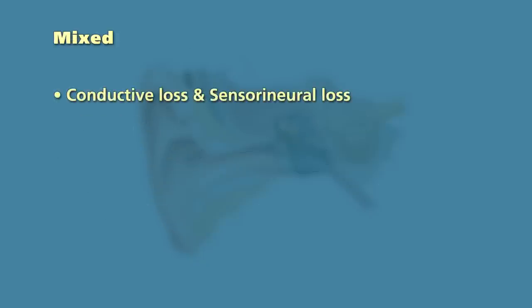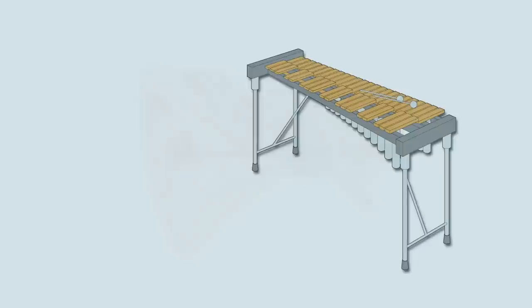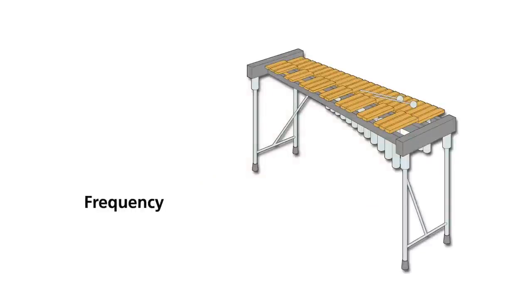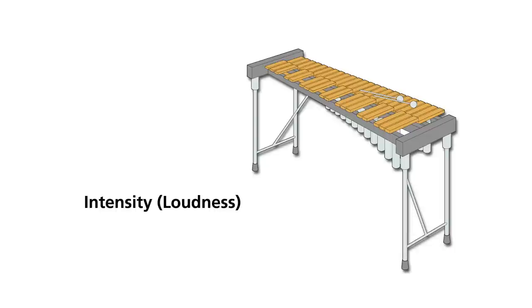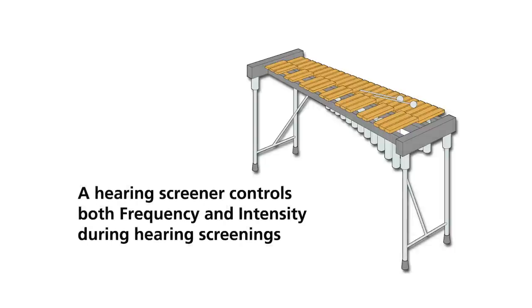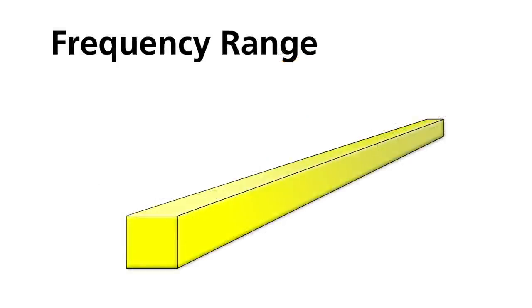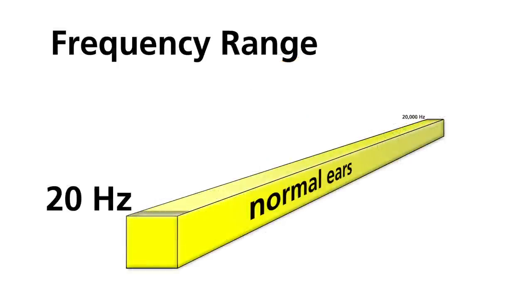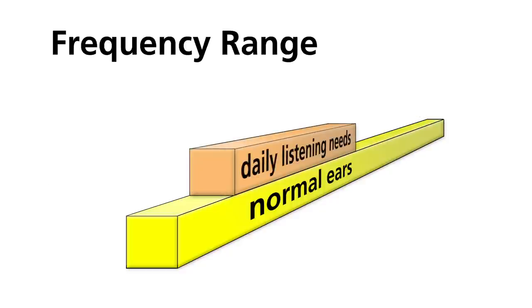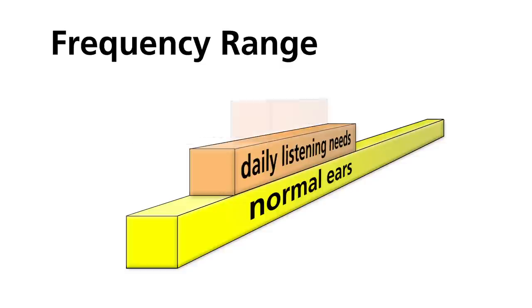A mixed hearing loss includes both a conductive and sensorineural hearing loss. Two important characteristics of sound are frequency, which we perceive as pitch, and intensity, which we perceive as loudness. A hearing screener needs to control both frequency and intensity during hearing screening. The frequency range for normal ears is 20 to 20,000 cycles per second, or hertz. The range of sounds for our daily listening needs is limited to a smaller frequency range — specifically, frequencies of 500, 1,000, 2,000, and 4,000 hertz are critical for hearing and understanding speech sounds. A child with a hearing loss in this frequency range has a distinct disadvantage compared with children who have normal hearing.